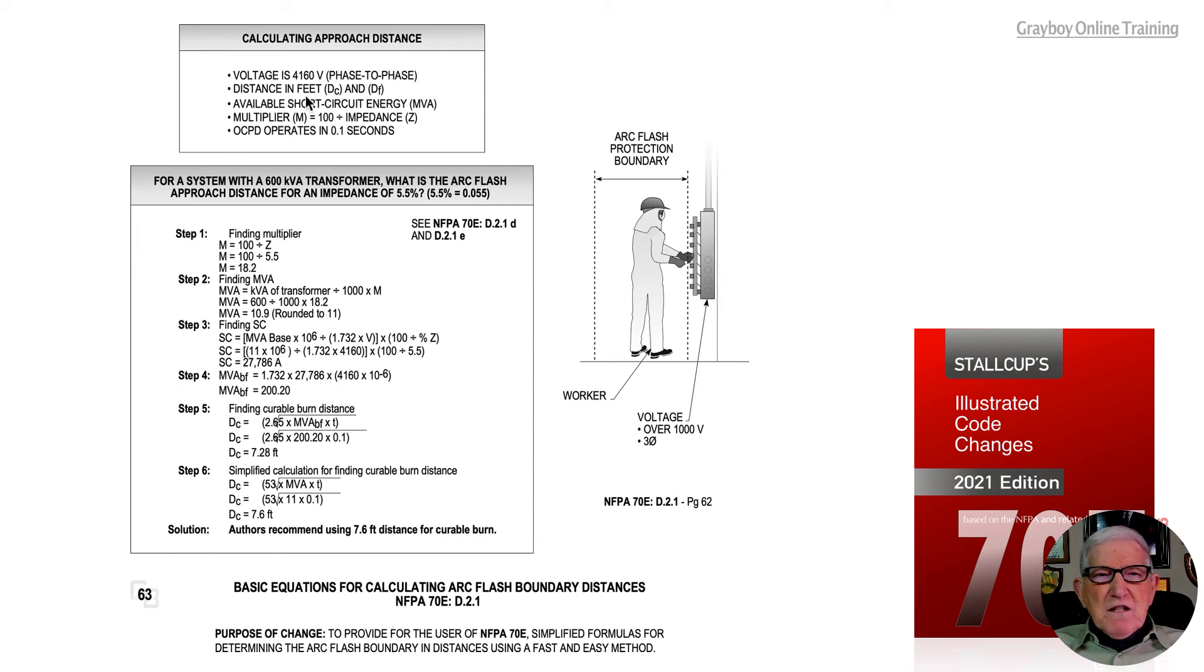We want to look at the available short circuit energy MVA. Develop a multiplier of 100 divided by the impedance of the transformer, and then the overcurrent device operates in 0.1 second, which is approximately six cycles.